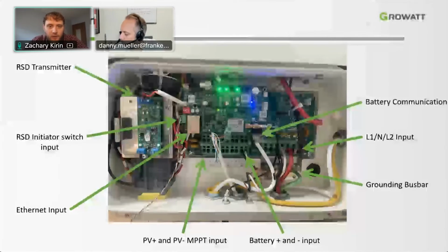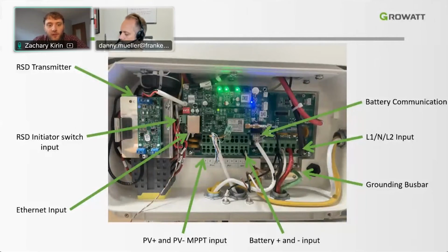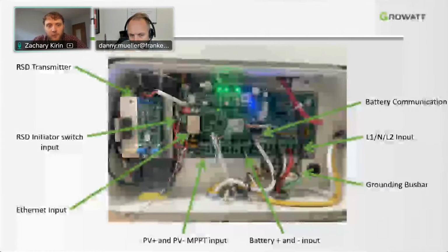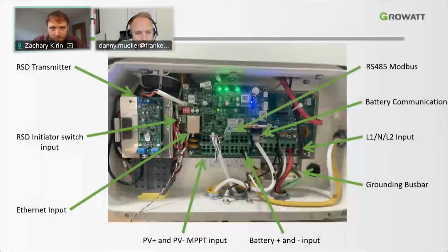And then the battery communication port as well. So this is where the battery communication is entering to the inverter. It's a separate LAN port, so it's shaped very similarly. So the RJ45 socket. So that's the Ethernet port and the battery communication port. So please don't mix those up. The Ethernet port is only for internet access.